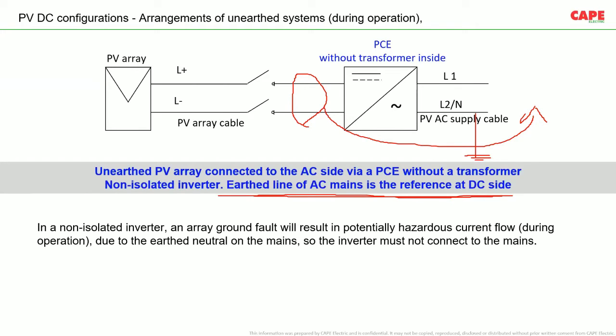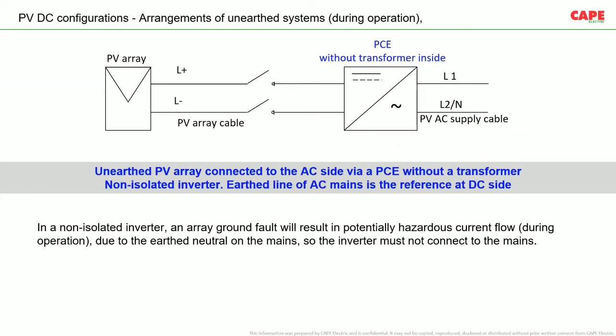The neutral under this condition is completely isolated. One moment, let me erase. Yeah. So here, what you are seeing in the picture is a PV DC side. You have the inverter which doesn't have electrical isolation. So the PV side is referenced to the neutral of the incoming supply, or to one of the phases of the incoming supply if it is three-phase.